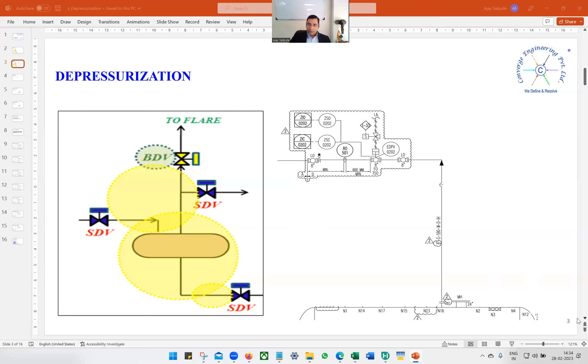When we say we are going to do the depressurization study, ultimately we are trying to find out what is the RO size — the restriction orifice size — and also the tailpipe size.